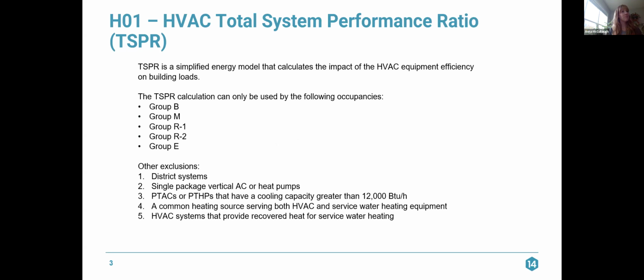So let's start talking about them. H01, HVAC total system performance ratio, TSPR. As you all might know, the TSPR pathway is a pathway that was created as an alternate for section C403, which is the mechanical section. And that is in section C409. The entire section, you still have to comply with the mandatory requirements. You completely substitute section C403 compliance with this TSPR method.